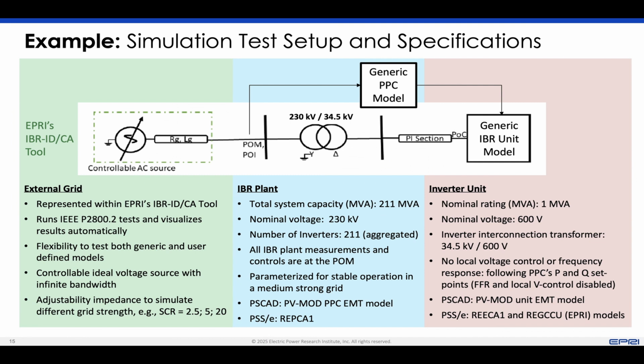And we are running both a PSCAD and a PSSE model using certain available generic models, which we can then configure in different ways. And the IBR units have their local voltage control disabled. Also, their fast frequency response is disabled. So they are following the power plant controller's P and Q set points. And it's really the power plant controller that provides the voltage response signals as well as the frequency response signals.